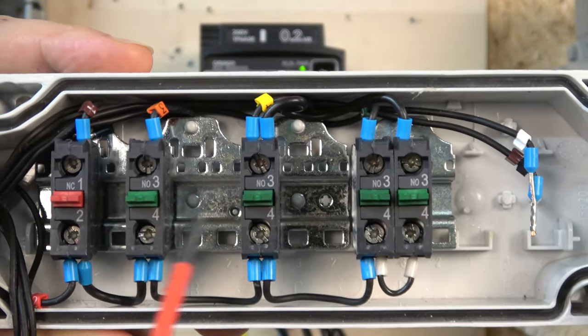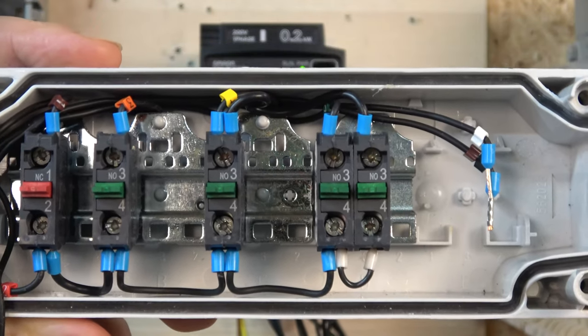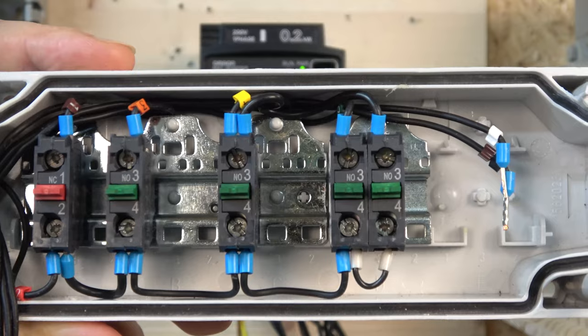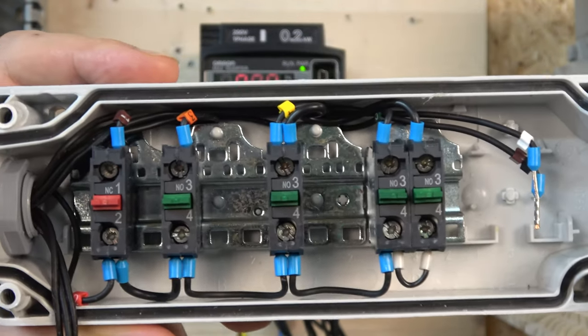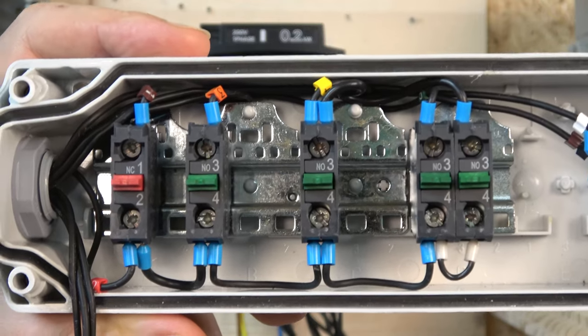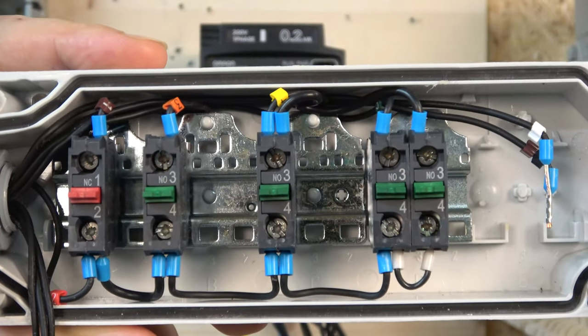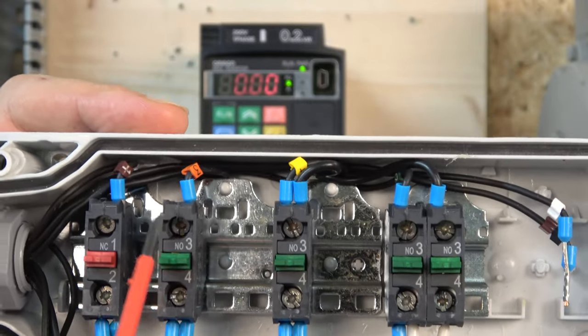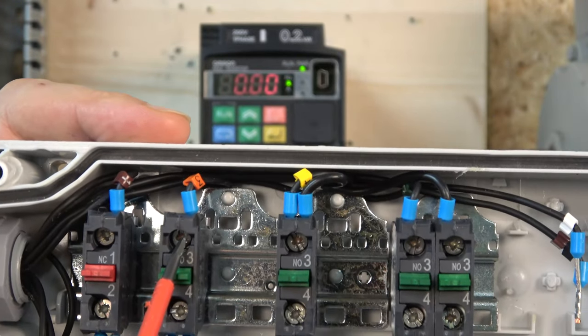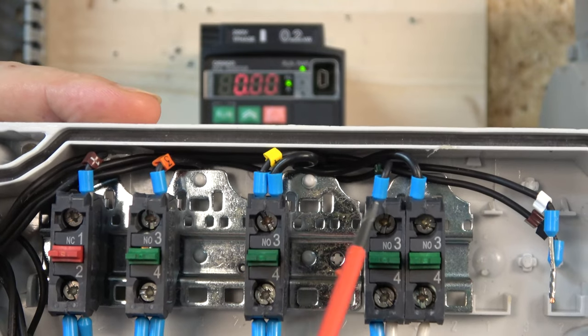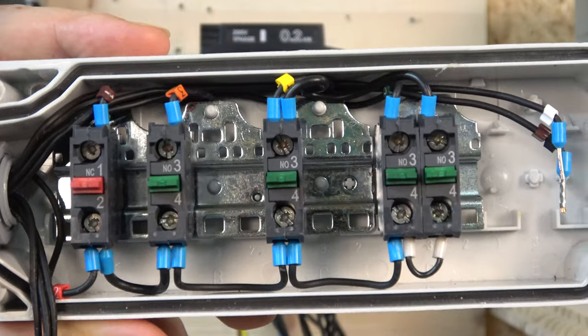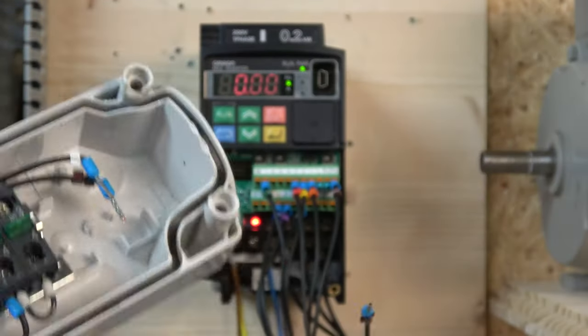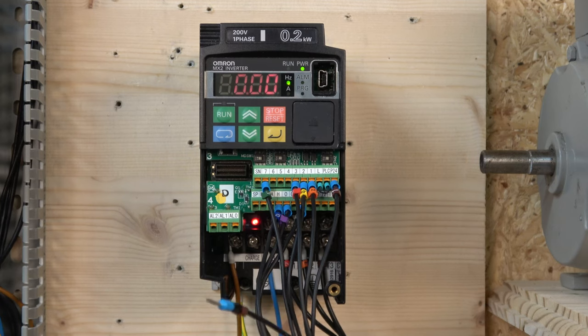So you get the run forward, run reverse, jog, and obviously jog another button to activate whichever way you want to jog because this jog requires the run signal. Any of those run signals, run reverse or run forward can be used. So you have to activate the jog and you have to activate any of the run signals. Unfortunately there is no option, at least I couldn't find it, to remove that so you can just use one switch for it. Run forward is terminal 1, run reverse is terminal 2, and jog is terminal 7. Everything is default, you don't need to change much. Pretty much everything we're doing here for this station is set to default.